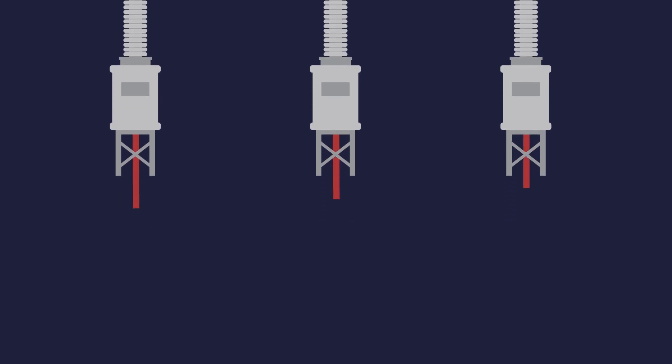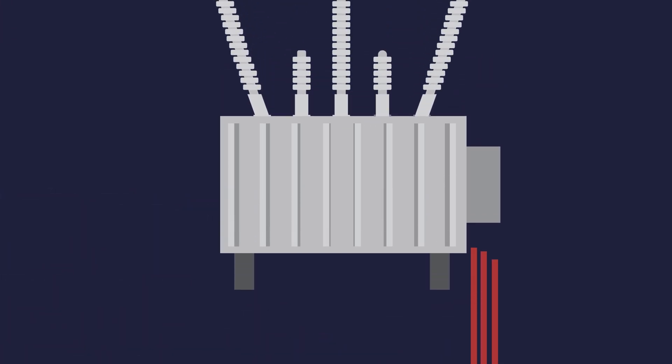Voltage Reference requires an additional voltage input from each bushing to be monitored. These voltage inputs can make retrofitting the reference methodology cost prohibitive if a voltage source is not already available, because of additional hardware and cabling.